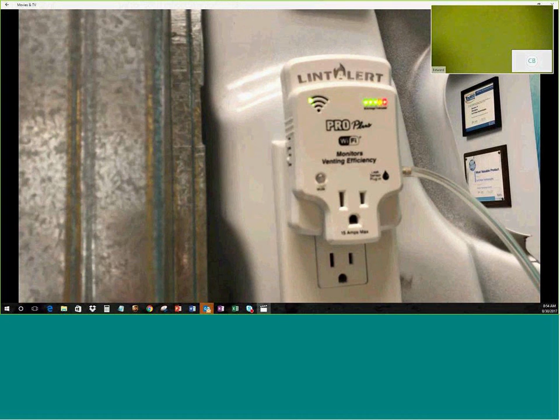Back on our app, it automatically advances from calibration, telling us we're done. Just to confirm we're all set, the dryer is on, and I'll click on this device to get a Magnehelic gauge readout of this specific unit. We have 0.411 water column inches on our app, and toggling back down here we have the exact same thing - it's telling us this LintAlert is all set and ready for that customer.